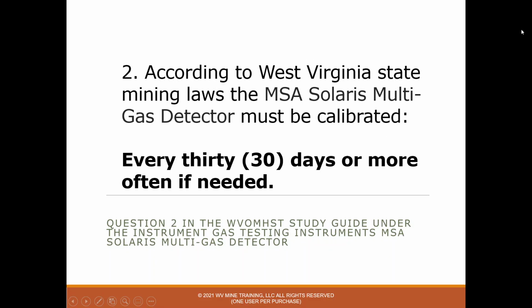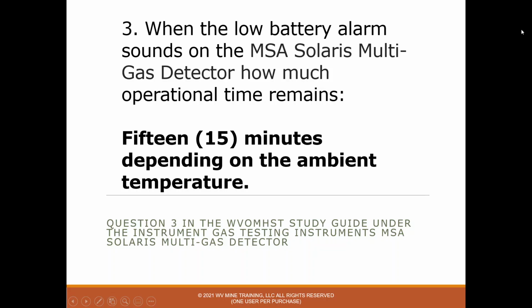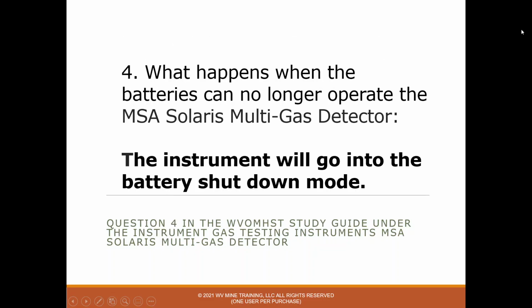Question 2, according to West Virginia state mining laws, the MSA Solaris multi-gas detector must be calibrated. And the answer to that is every 30 days or more often if needed. Question 3, when the low battery alarm sounds on the MSA Solaris multi-gas detector, how much operational time remains? And the answer is that's 15 minutes depending on the ambient temperature. And the ambient temperature is just the temperature of the air in the mine where you're at. Question 4, what happens when the batteries can no longer operate the MSA Solaris multi-gas detector? And the answer to that is the instrument will go into the battery shutdown mode.